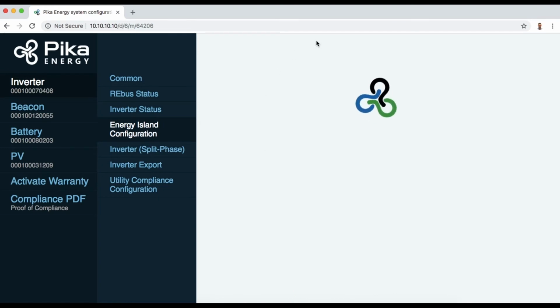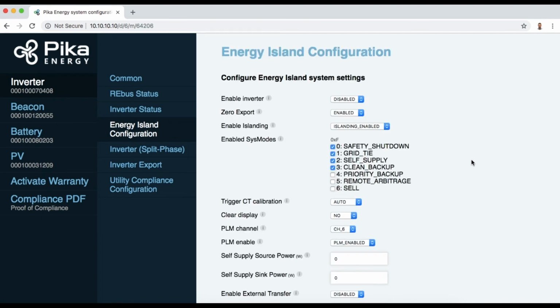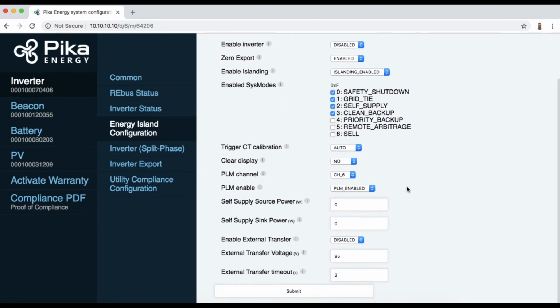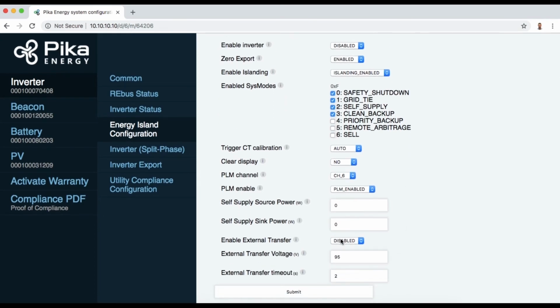From here, I'll press submit, and in a moment you'll be able to see that zero export is enabled and the customer is locked out of the system modes that we adjusted. So as you can see, zero export is now enabled, our islanding is enabled. The customer has access to safety shutdown, grid tie, self-supply, and clean backup. And their external transfer switch is disabled because they're not using one.